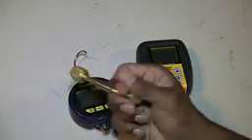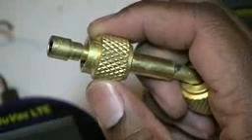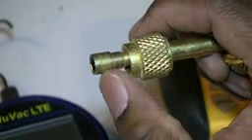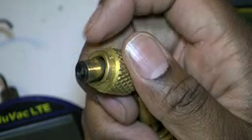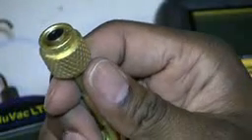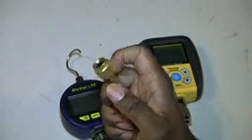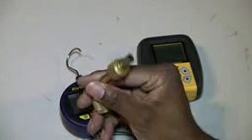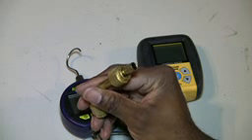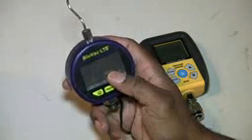What I also discovered with the accessory piece for the NuVac — the bell at the tip and the bell at the other end — both had hairline cracks in them. Hairline cracks on both ends, which kind of let me know that I may have tightened down too tight trying to get this to read initially. So I ordered a new one and started using it, and now I'm starting to get the gauge to work.